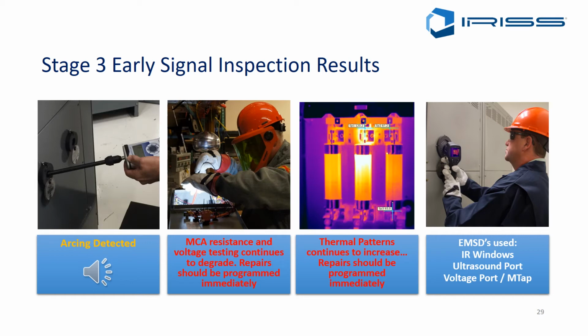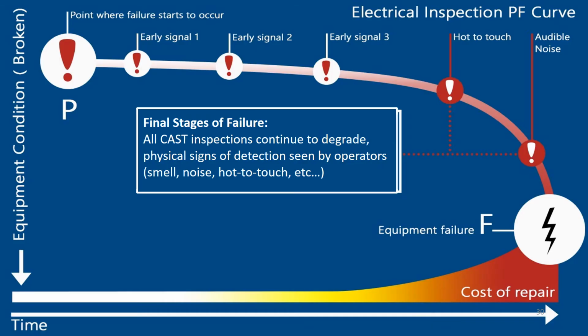So a very, very distinctive sound. Obviously, again, at this stage, the motor current analysis and the voltage and current testing are going to be showing significant signs of failures. Your thermal patterns are going to be critical. So again, all this is done through your EMSDs. Totally safe, quick, efficient, and the panel remains enclosed and guarded in a safe condition. Okay, so very, very simple process to do to make these measurements.